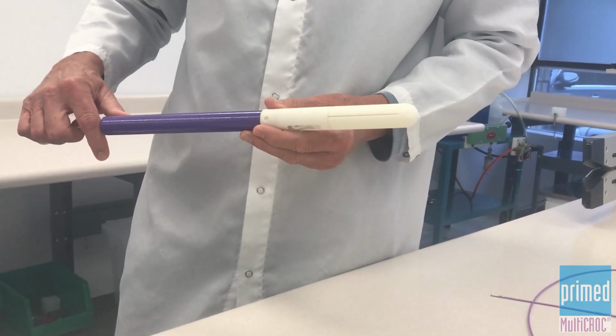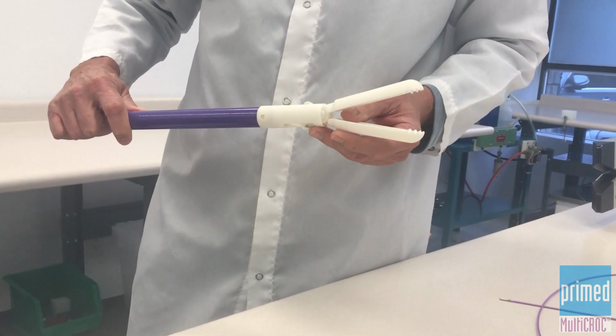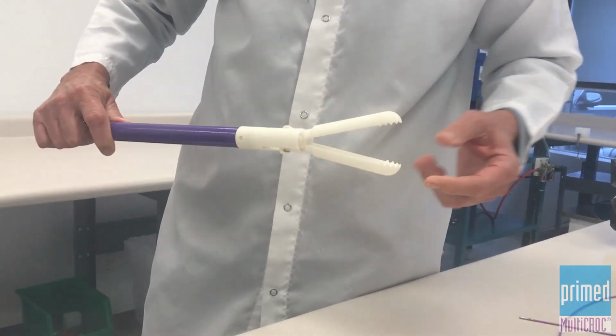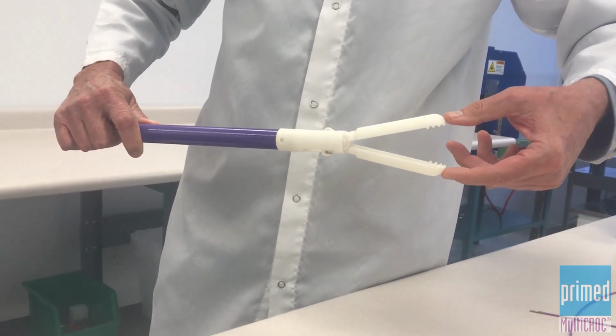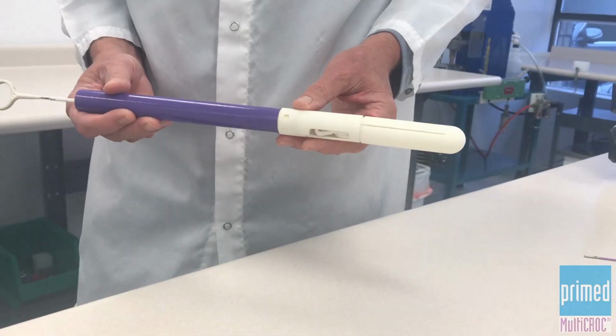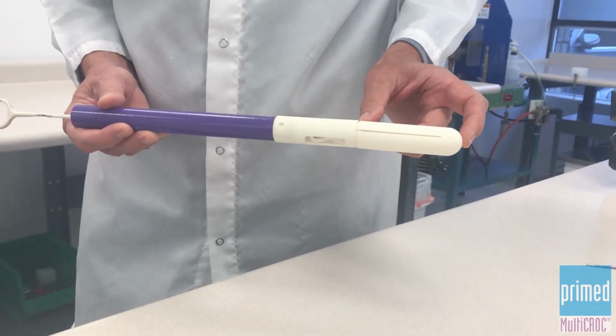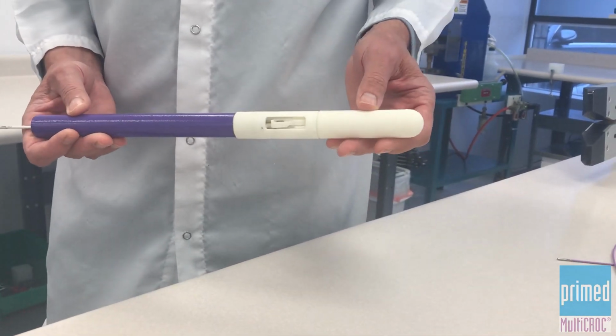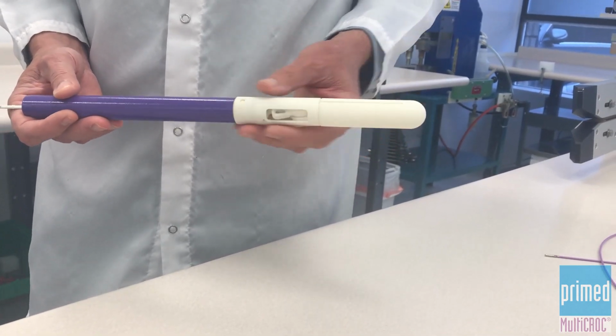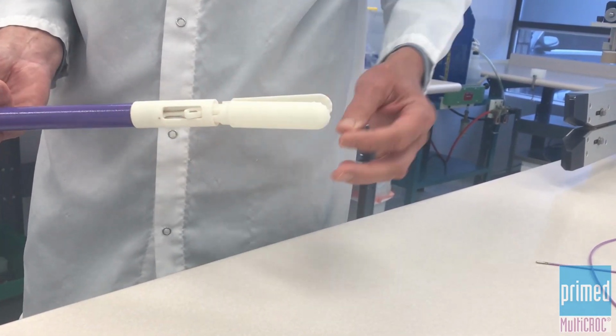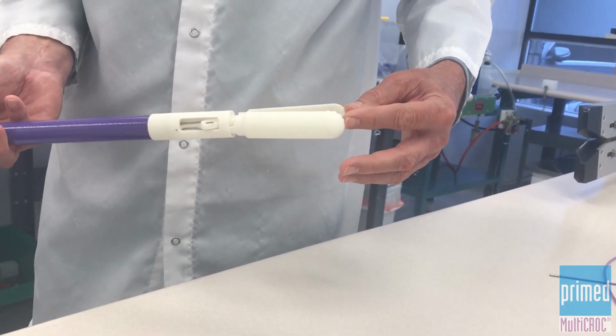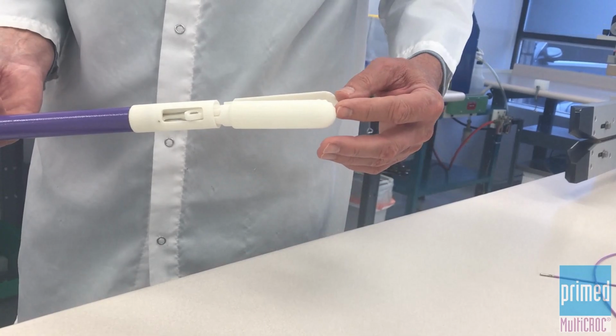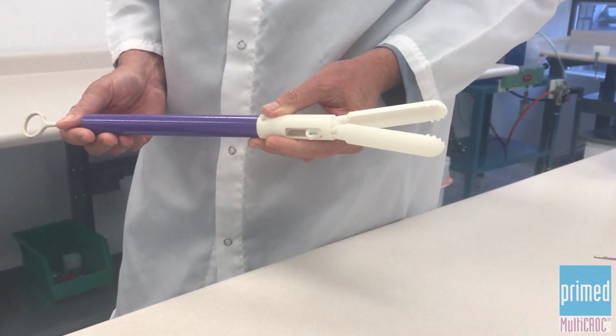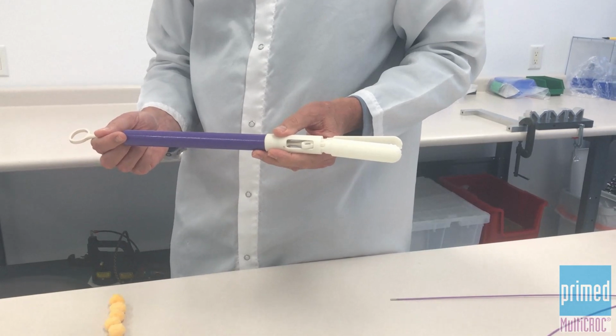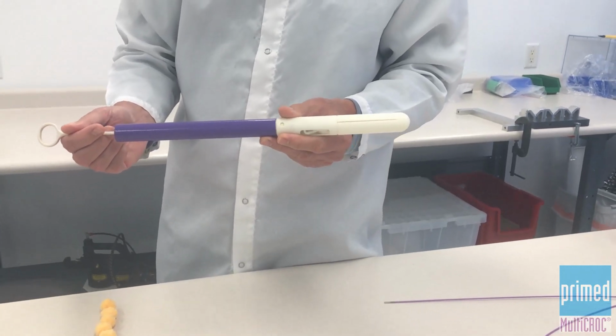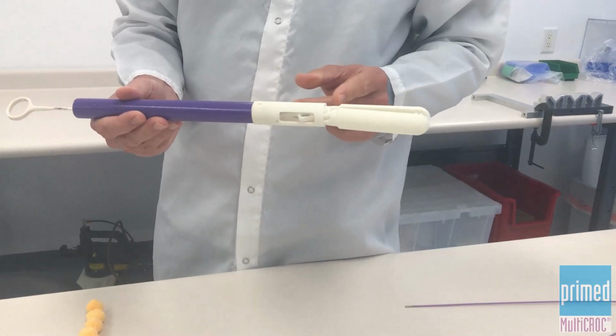The jaws open to a smaller angle than the standard biopsy forceps. The opening of the jaws at the tips is approximately 4 to 4.5 millimeters. As mentioned, the jaws are longer in the MultiCROC biopsy forceps. If we were to introduce longer jaws in the standard biopsy forceps, the clamping force at the end of the jaws would be greatly diminished. It has to do with geometry and the vectors and the way the forces work. In order to overcome that, our patented mechanism moves the jaws slightly back. This movement is approximately 1 millimeter in length.